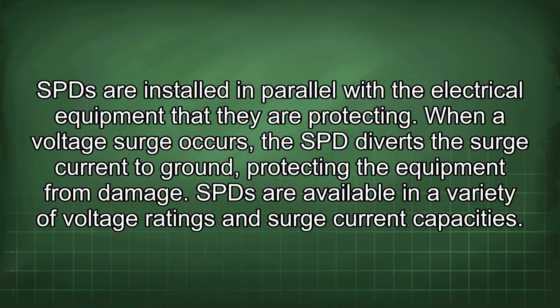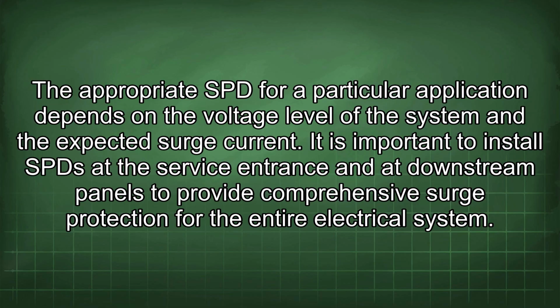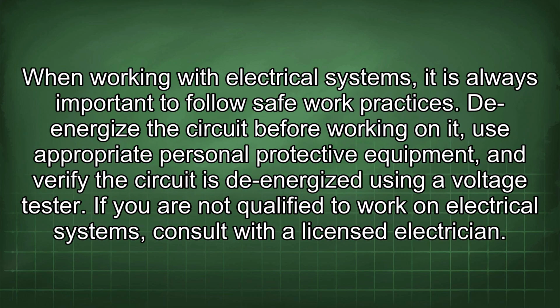SPDs are available in a variety of voltage ratings and surge current capacities. The appropriate SPD for a particular application depends on the voltage level of the system and the expected surge current. It is important to install SPDs at the service entrance and at downstream panels to provide comprehensive surge protection for the entire electrical system. When working with electrical systems, it is always important to follow safe work practices.